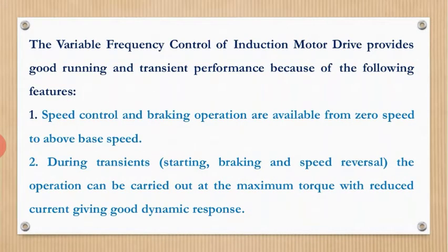Second one, during transients, that is starting, braking and speed reversal, the operation can be carried out at the maximum torque with reduced current, giving good dynamic response. This is another feature of variable frequency control of an induction motor. This is very important. We can't achieve this with the help of stator voltage control. The torque will be less.